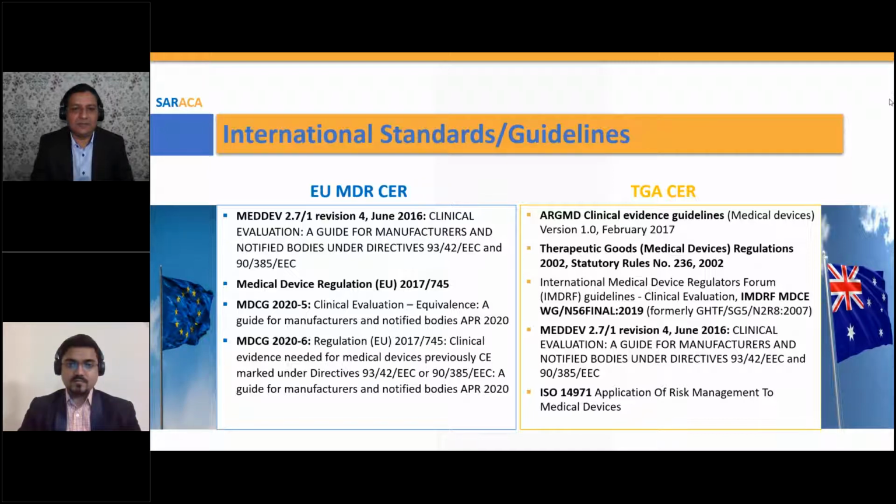And the International Medical Device Regulators Forum guidelines, the clinical evaluation, which was promulgated in 2019, and the MedDev Guide for Manufacturers and Notified Bodies for Clinical Evaluation, released in June 2016, with also a heavy dose of ISO 14971 and the application of risk management to medical devices.